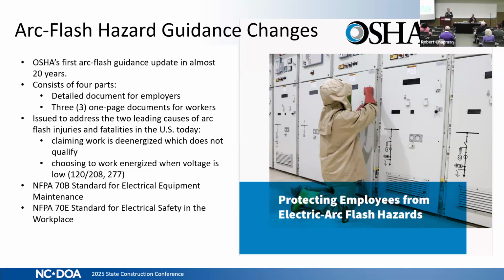So is it a life safety system like a generator and emergency lighting, or is it just incidental use, like receptacles or something supplying some sort of convenience load, right? So you categorize your equipment by age, by equipment type, switchboard, panel board, and how critical the equipment is to your system. Then it allows you to follow the NFPA 70B recommended practices and address any risks that might arise and be in compliance with OSHA.